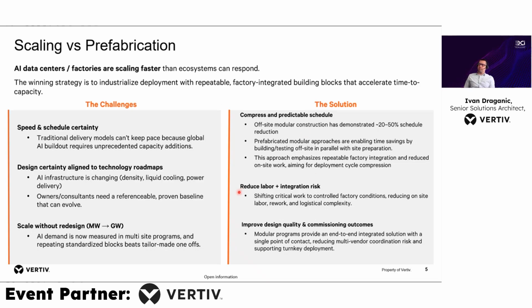The second big point is reducing labor and reducing integration risk on site. With the prefabricated solution, we need a lot less labor, especially highly skilled, qualified labor workers on site. That's because everything was built in the factory, which has already pre-tested and done point-to-point tests for BMS, commissioning the data center up to level 3. Levels 4 and 5 we still have to do on site, but overall it takes a lot less time and the labor required is significantly reduced.